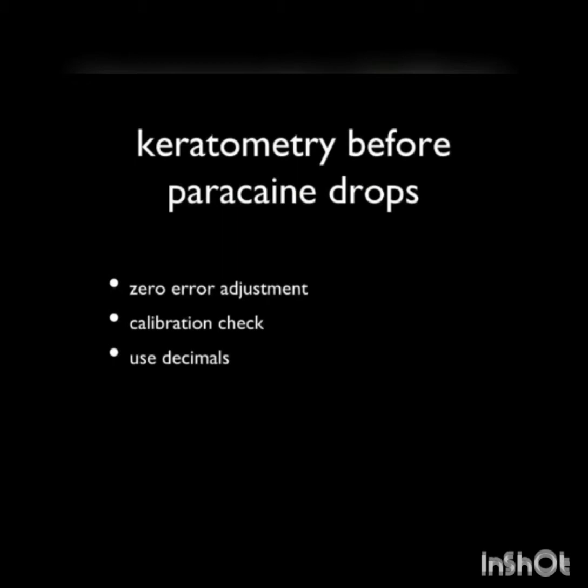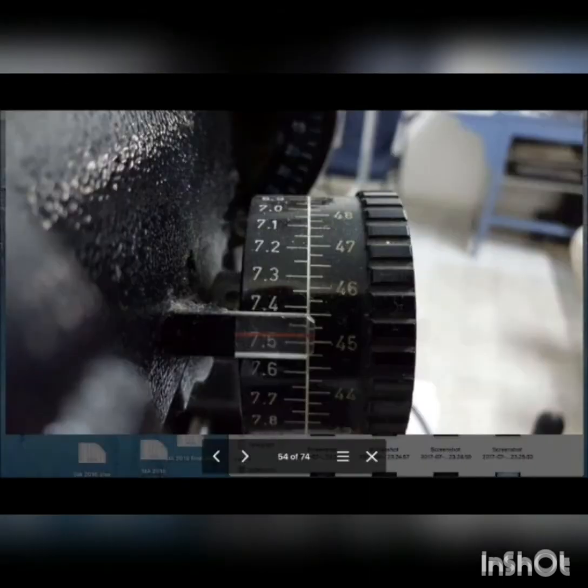To take a proper keratometric reading, remember: keratometry should be done before applying any drops on the cornea — before applying paracaine eye drops. Once a month, please do a zero error adjustment and also do a calibration check on your instrument. You should start noting down keratometric readings using decimals and not 0.25 steps.